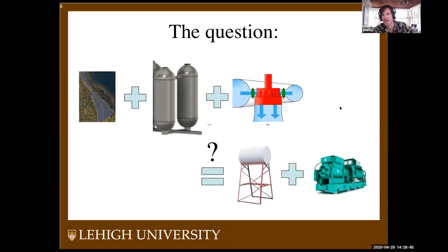So let's look at our parameters. One unfortunate restriction is that at the base of each tank, buried in an unnegotiable amount of concrete, is a single 32-inch outlet, which really limits the flow rate you can get out. Another bleak data point is that it's a shallow gradient, not at all what you'd traditionally look for in pumped hydro. We're looking at a 1% gradient over 2.5 miles. At Yards Creek, by comparison, the gradient was like 35 to 40%, and at most 1/8 of a mile away. Very different.